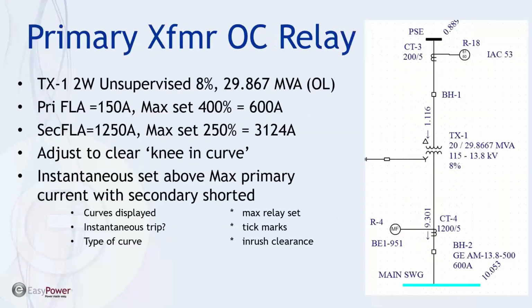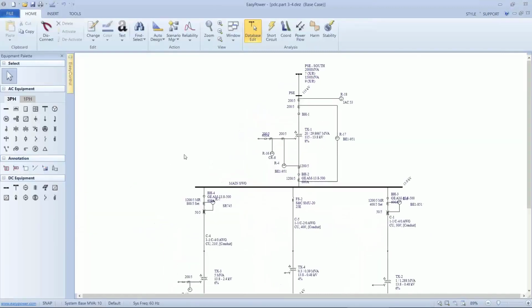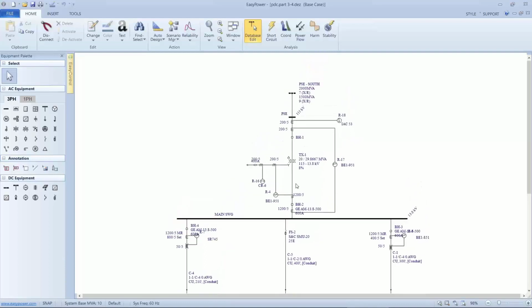Okay, so let's jump into EasyPower and talk about this. Just a side note, this file that I'm using is, for anyone that has the tools, in the sample folder. This is Protection 1, and it's worth playing with these if you want to check up on what I'm doing. Okay, so what we're talking about is this system here. I'm going to selectively pick out the primary overcurrent relay, its CT, the breaker, the transformer, the downstream overcurrent relay, its breaker, and then plot the TCC curves.